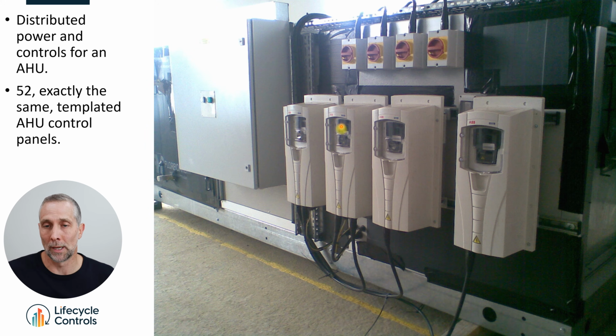So this was all installed at the factory: duty standby, supply and return fans, and here's my control panel. To be honest, it turned out that this wasn't actually worth it. We stopped doing it. It's really difficult to prefabricate controls offsite on AHUs because the AHUs get delivered in modules and get bolted together. So we were trying to do different types of cabling methods with plugs to plug through, which is too hard. A bit of damage also happens on the AHUs.